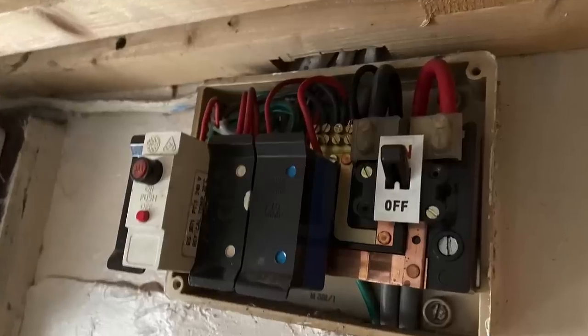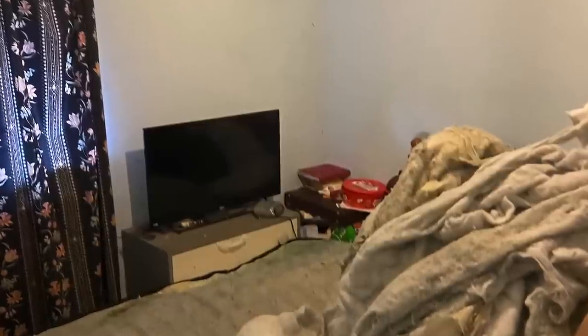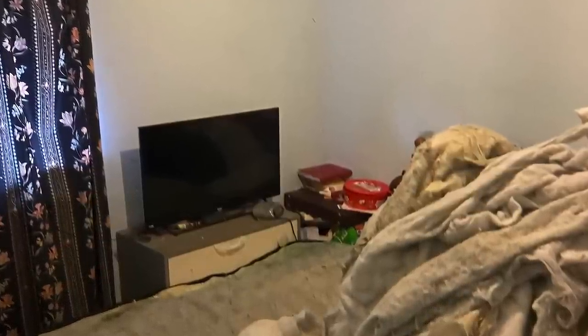Sometimes you have to say, 'Well, actually, my safety comes into it.' We can maybe just do a visual inspection, like I did in this one — I could see the board didn't have any RCD protection. It's similar to the other flats, they're all the same age with the same sort of install. We can't refuse to work in a property just because we don't like the decor. Sometimes it's challenging, and photographs showed how challenging it was to get to different aspects.